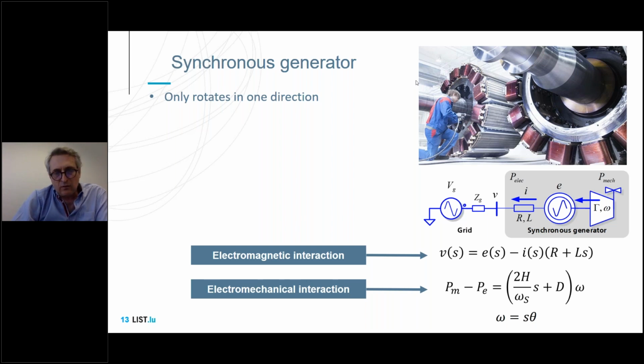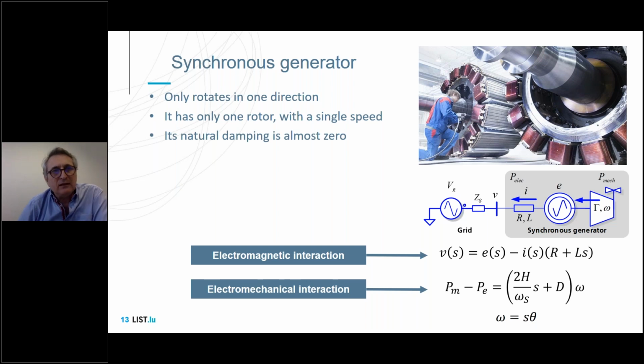Only with positive sequence. Therefore, the synchronous generator is only rotating at a single speed. It's really interacting with the fundamental frequency, but not naturally with harmonics or subharmonics. The damping of the synchronous generator has been a problem from the very beginning. The natural response of a synchronous generator is undamped, and it's necessary to integrate some dampers or additional mechanisms.